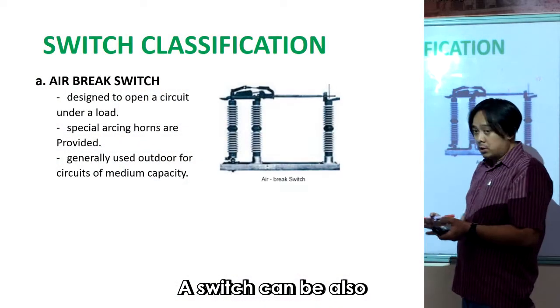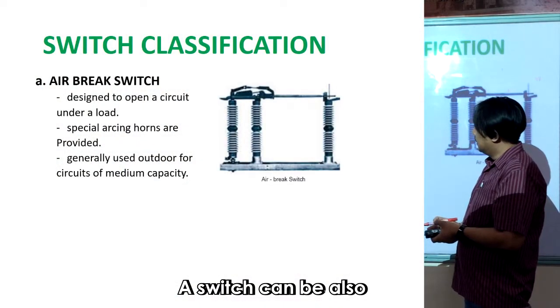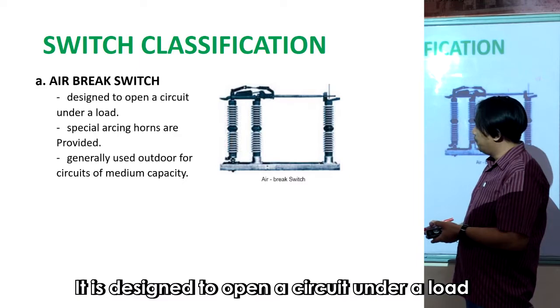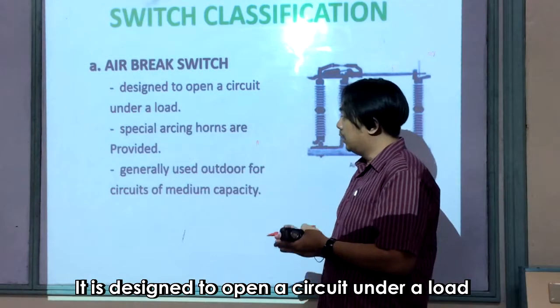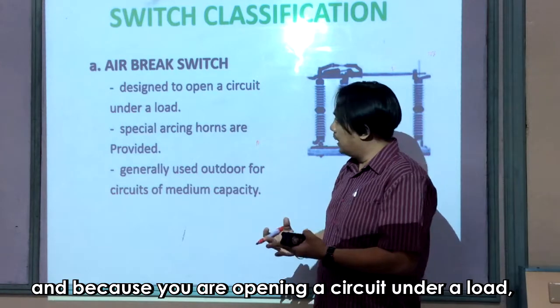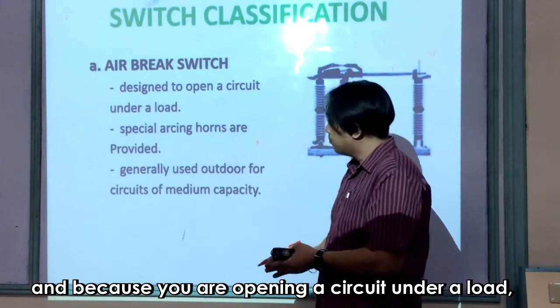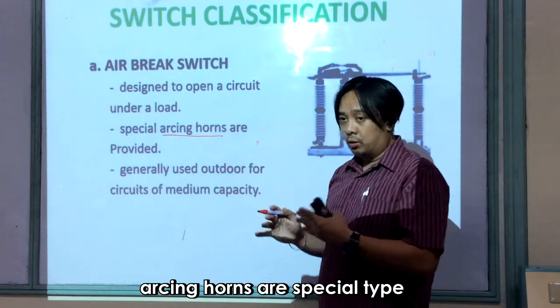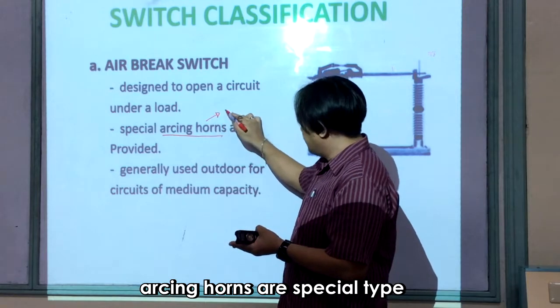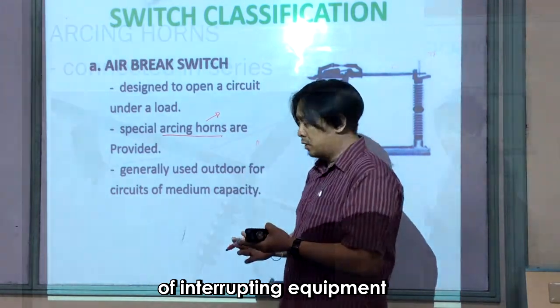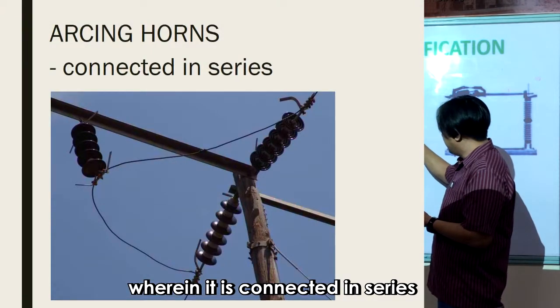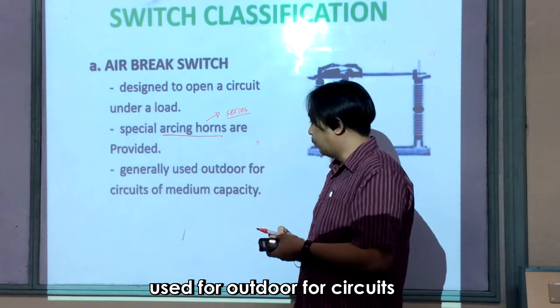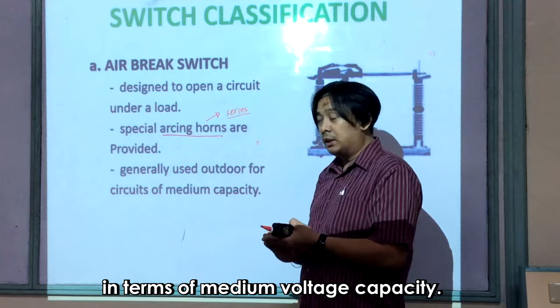A switch can also be of different types. First, we have an air-break switch, which is designed to open a circuit under full load. Because you are opening a circuit under load, there are special arcing horns connected in series to prevent arcing phenomena. It is generally used for outdoor circuits in medium voltage capacity.